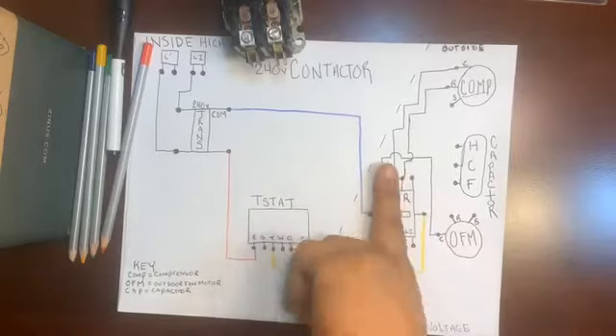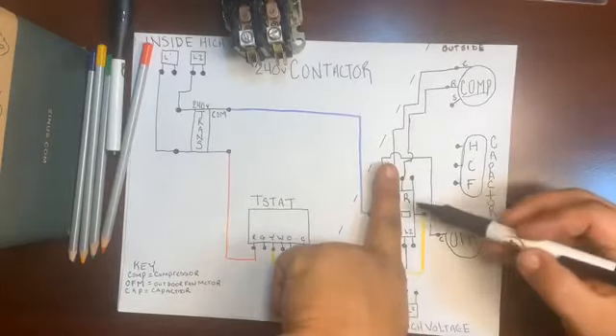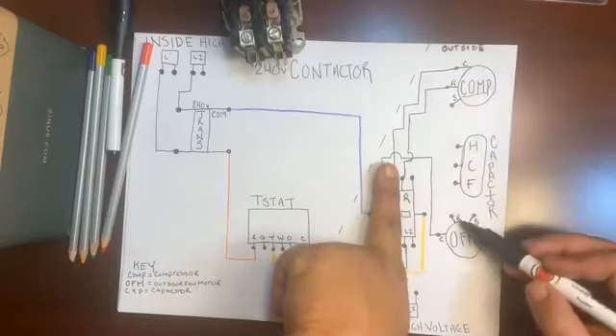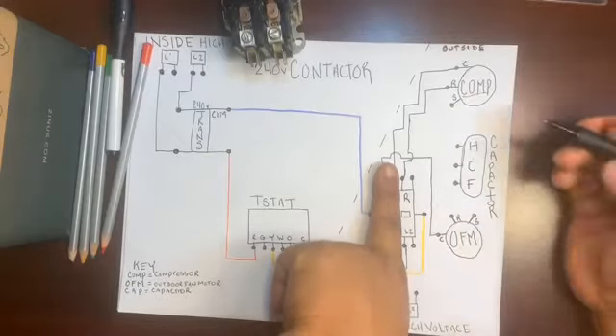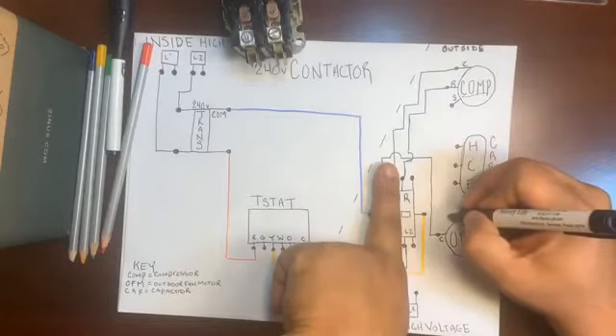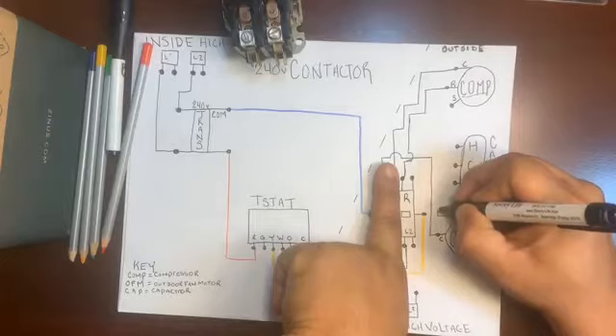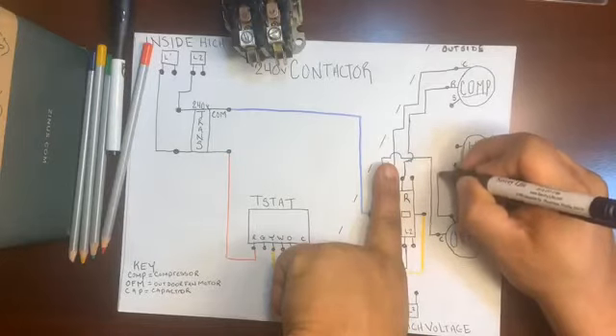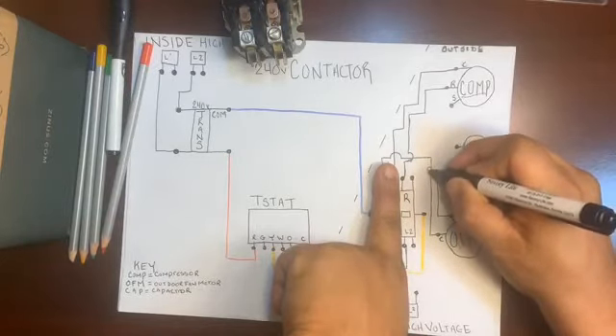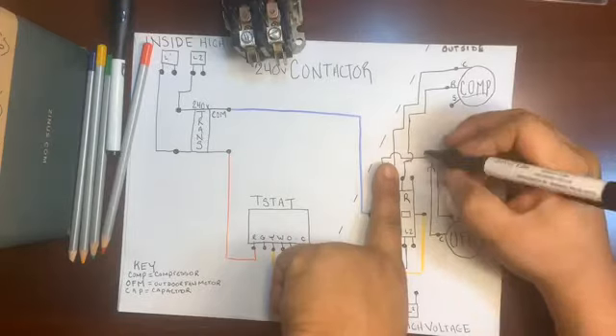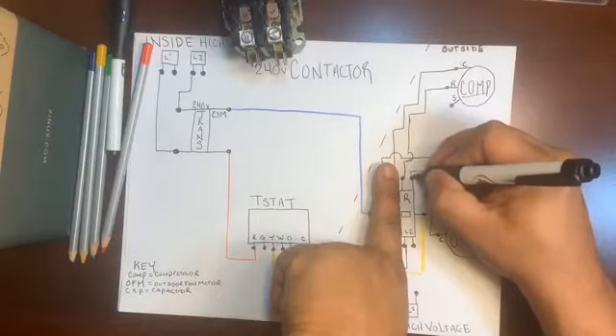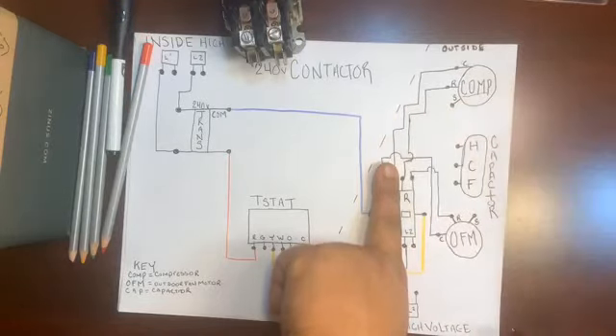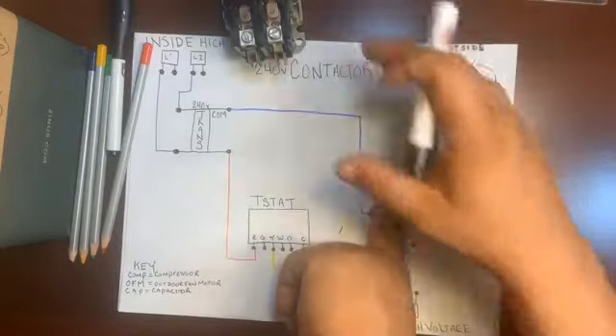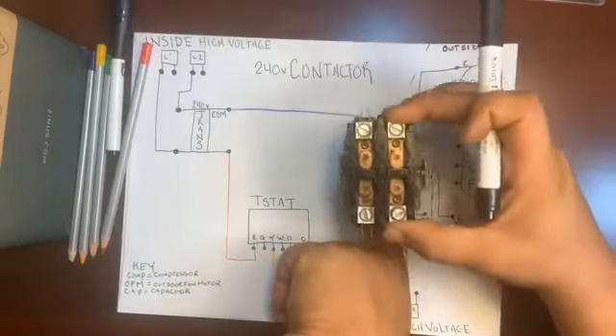Okay, so now we're working on the run side. We've brought the run down from the compressor. We have a run on the outdoor fan motor. We're going to bring it over also. Bring it over, travel up, make a bridge, and come on back down to the run side of this 240 volt contactor.